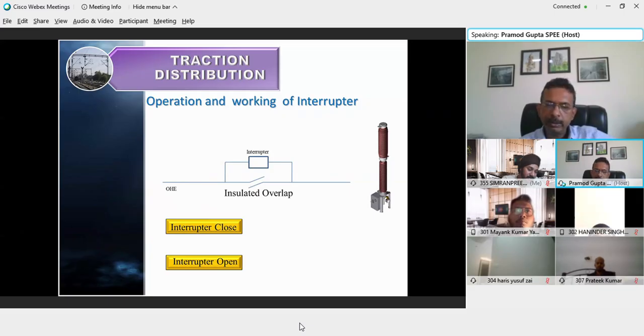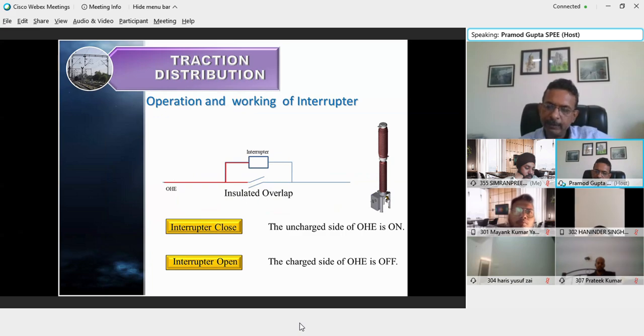When the interrupter is not closed, the OHE is restricted to the left hand side of the interrupter; it does not get extended to the other side. Suppose I want to extend the OHE from the left hand side of the screen to the right hand side, then we close the interrupter and the power supply gets extended to the other side. This function is also performed when I want to extend the power supply from one TSS to another TSS. When I switch off the interrupter, the power supply which was extended earlier is no longer available on the other side, and normalcy gets restored. So this is how the interrupter is operated in the system.